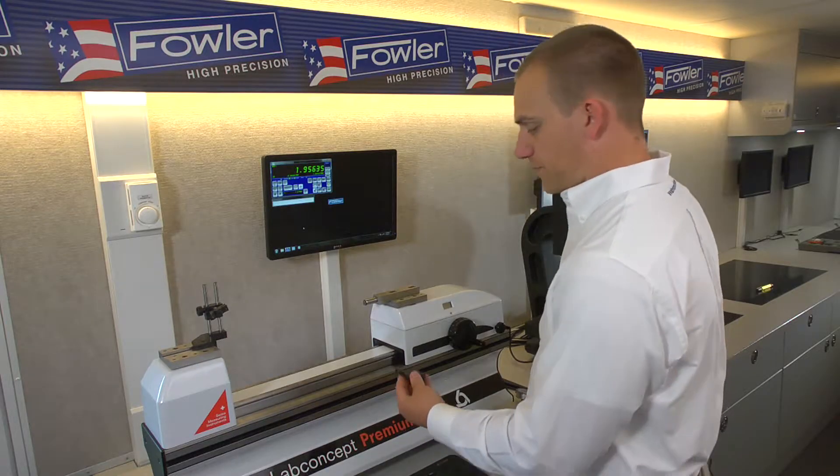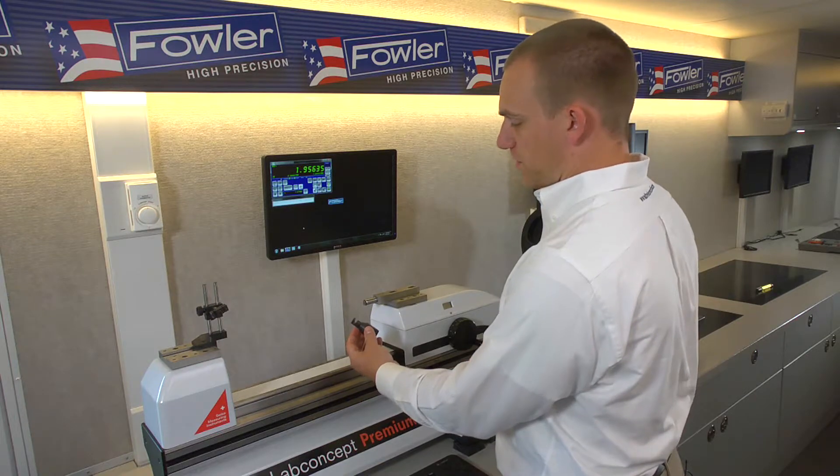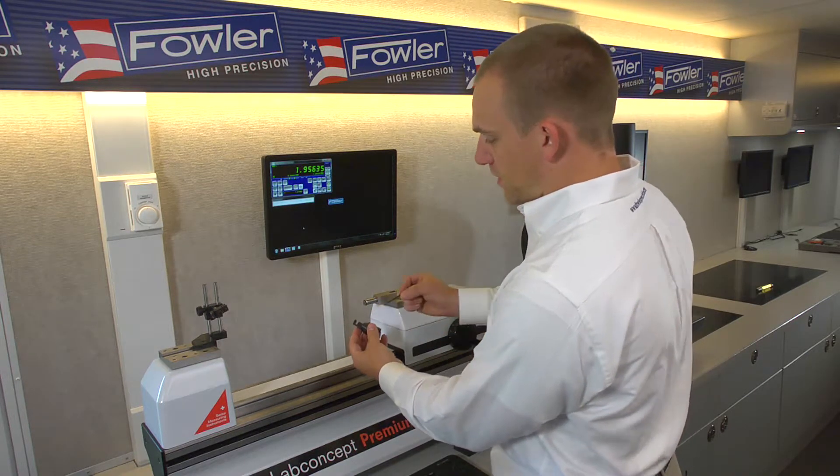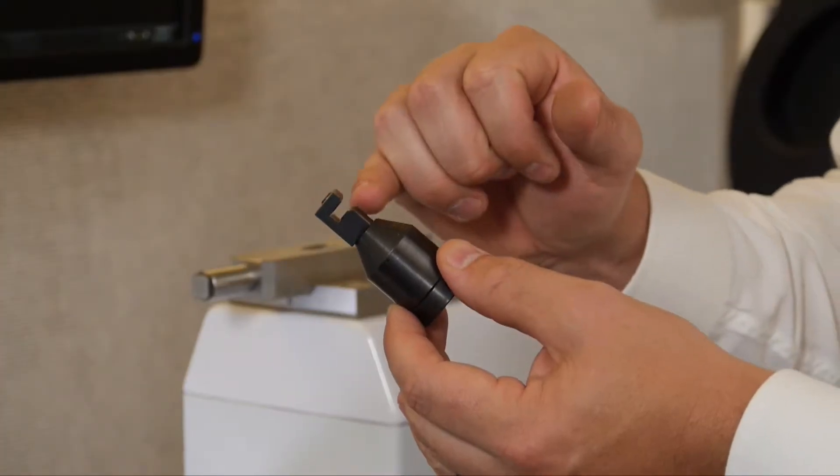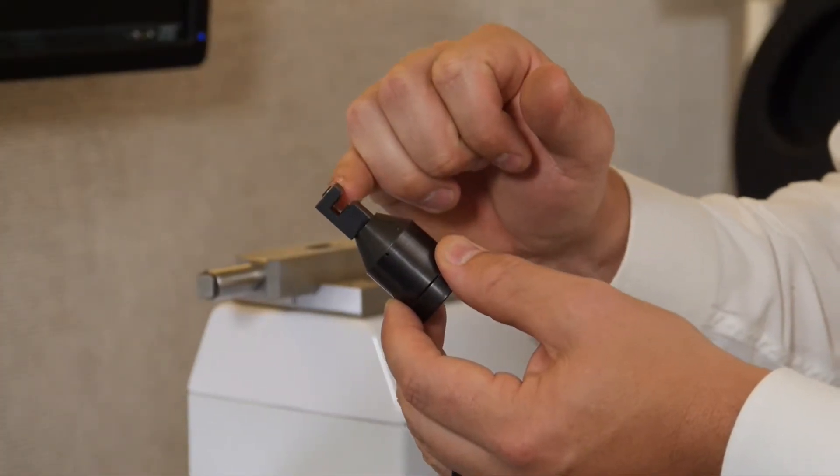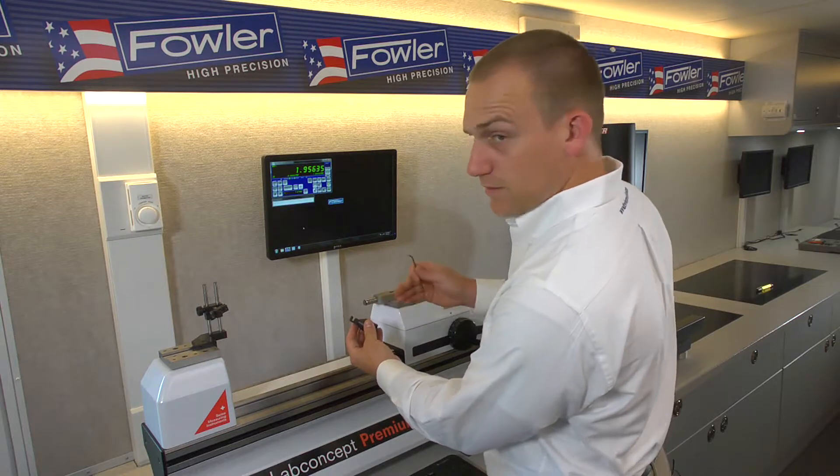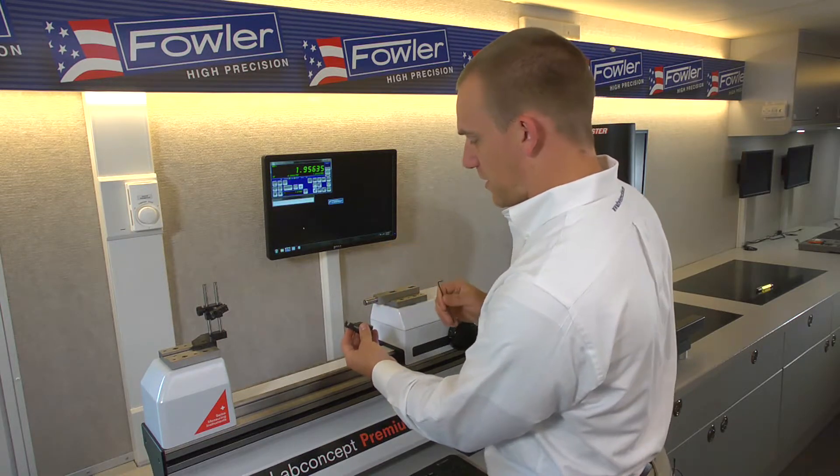For the right anvil we have this device here which slips over the standard anvil set. And this has a gap in here with two contact points so you want to get your test indicator point between the two so you can touch off the left and the right side to check it for linearity in both directions.